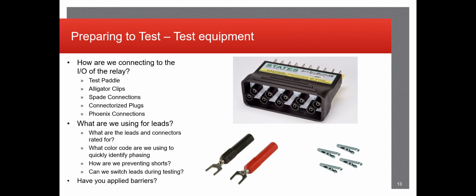You can actually move them around depending on the test too, which makes life a lot easier during the testing process. But again, if you don't have test switches available to plug in the paddles, you'll most likely be utilizing these little forks down here in the bottom left. These are what you'll plug in directly in the back of the relay to the terminal blocks.